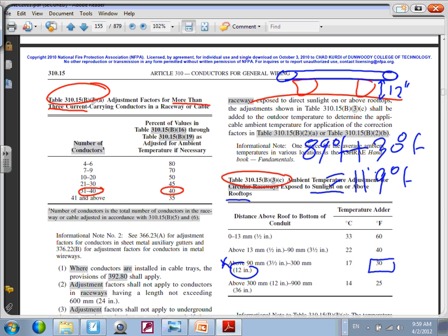Okay, what is strictly roofs though? Commercial roof. Mostly this application is for a commercial roof. But now with residential, it applies when you put a solar system on. But on a commercial roof, guys, you will have an air handling unit on the roof, like a rooftop cooling tower. For my cooling tower, two ways: either you poke right underneath it and tie in so you don't put the conduit on the roof, or you put the conduit below the roof in the building. If you put it above the roof, then you have to pay attention. When we do our field trips, you're going to see tons of conduits running on the roof of a commercial building.